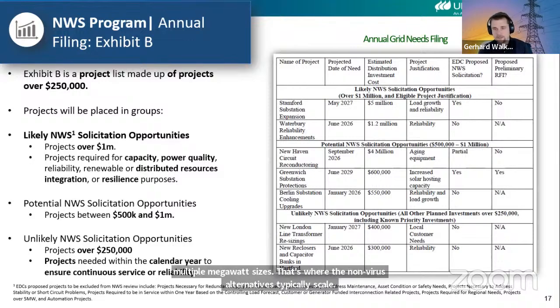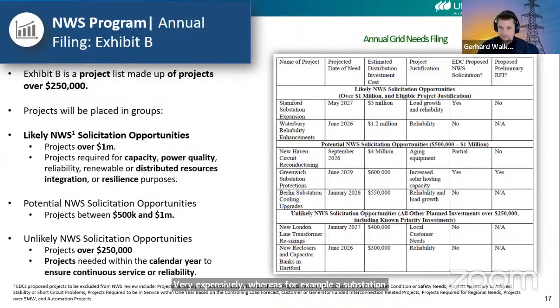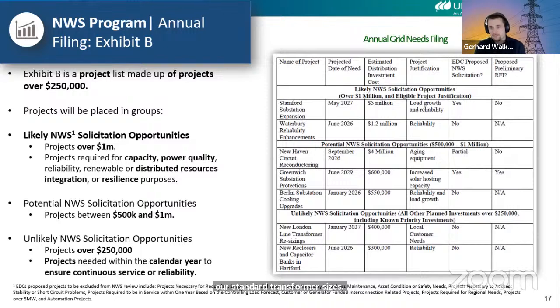Whereas, for example, a substation upgrade — making up numbers — if you're going from a 40 to a 62 MVA transformer, 62.5 MVA is a standard transformer size, so we go to that size regardless of how much that is. If you need 20 megawatts, it gets very hard for the non-wires alternative to compete, because that battery scales up in price the bigger the deficit is. So typically a relatively high cost compared to a relatively low need works best for non-wires alternatives.